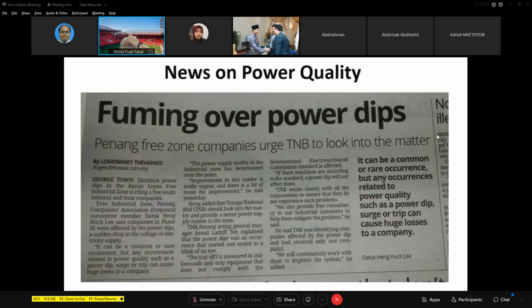Okay, just now I showed a news clipping on undervoltage, overvoltage and outage. Now I'm showing the news clipping on power quality, in particular voltage dip. This was reported in Penang a few years back, where customers in Penang are still angry. People say yesterday we had a power dip in Penang, last week, almost every week. So the customer association, FREPENCA, which stands for Free Industrial Zone Penang Company Association, are upset because, as explained just now by the three issues, the magnitude of voltage, duration, and phase imbalance cause critical equipment to be affected.